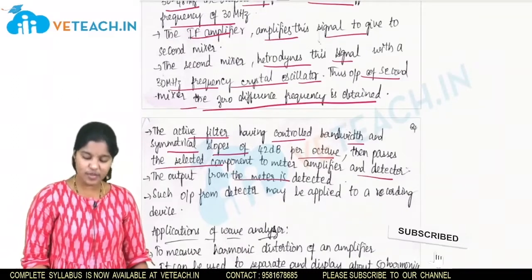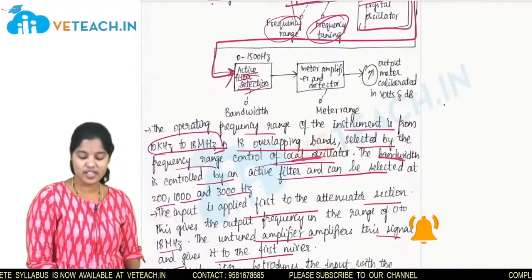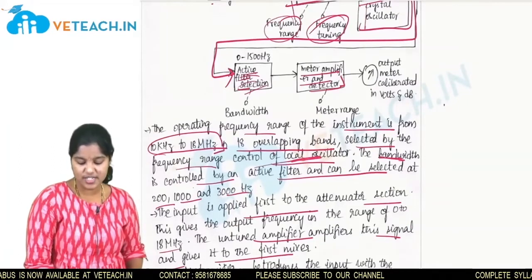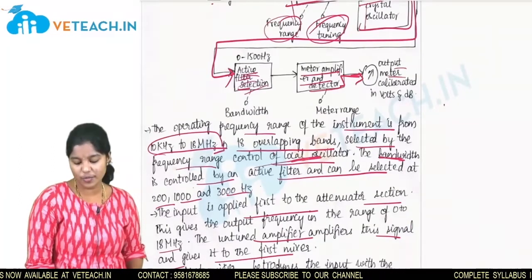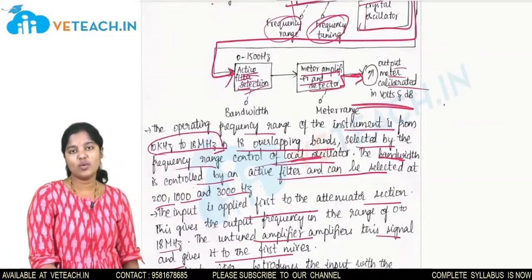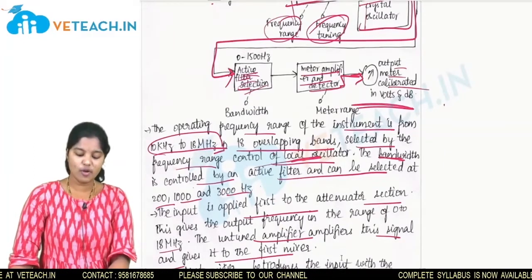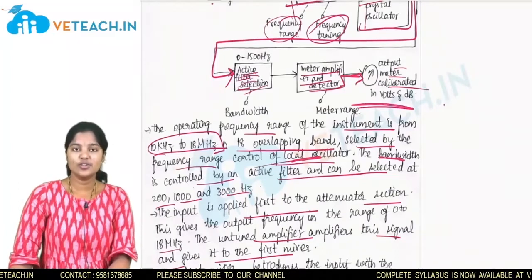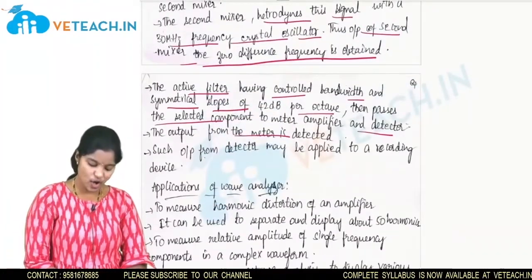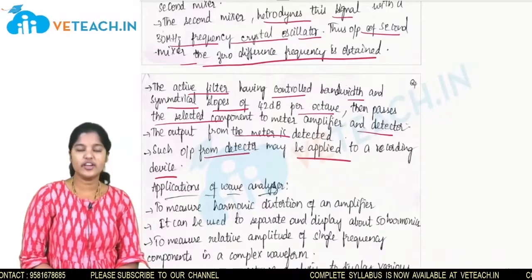The output of the meter is detected and passes to the active filter section, then the meter amplifier and detector section. The output meter is calibrated in volts and dB. The output from the detector may also be applied to a recording device.